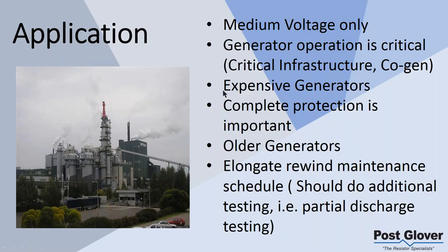To be honest, if you have a new generator, this is not likely. I don't have any data to support that, just common knowledge. These types of faults, when you have insulation breakdown and stuff like that, usually happen with older generators. It's much more likely for it to happen with older generators. That brings up the point that complete protection is important. For example, you're an engineer and you think, I'm good on all my faults, I'm low resistance ground protected, I'm good to go. But you didn't realize you didn't have this protection when it comes to stator faults. It's not likely, but I don't like the idea that we're not protected. So that's another option.